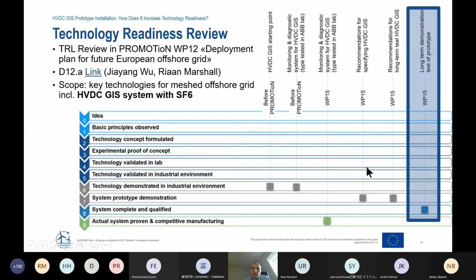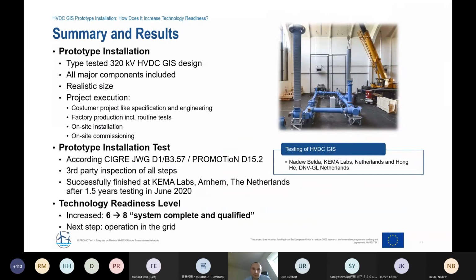And what we've done then in PROMOTioN, we have worked to get recommendations to specify an HVDC GIS and also to long-term test an HVDC GIS. This is already a first increase. And then we have done the long-term prototype installation test, including the installation and everything. And with this, we now have a technology readiness level of 8 for the complete system HVDC GIS. So basically, this is the highest level that you can reach, I would say, in a lab. And the next step is then really an on-site and real world service of the technology.